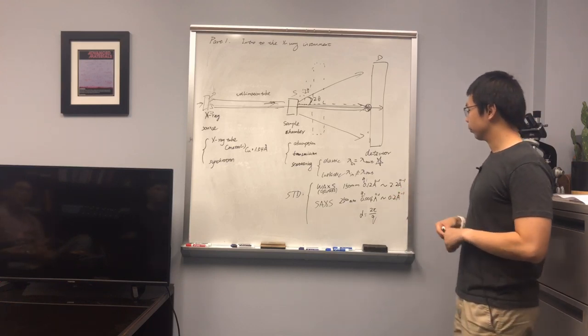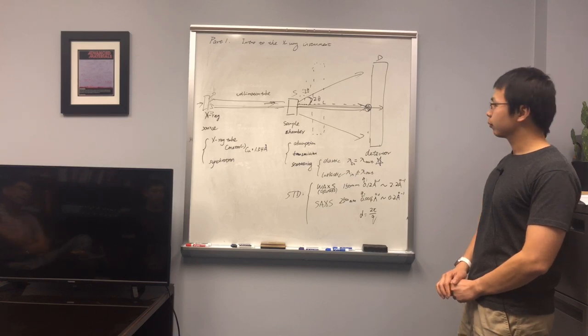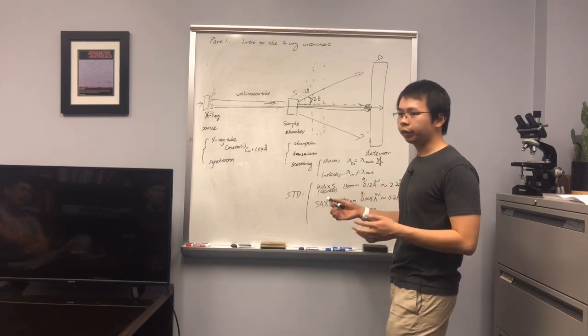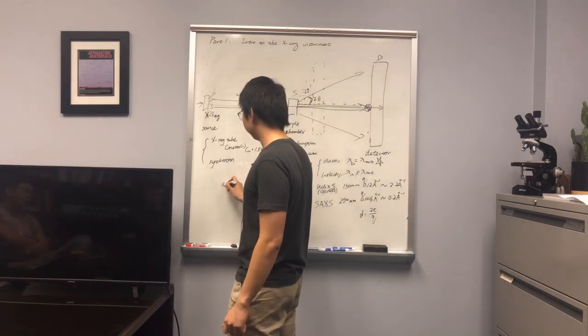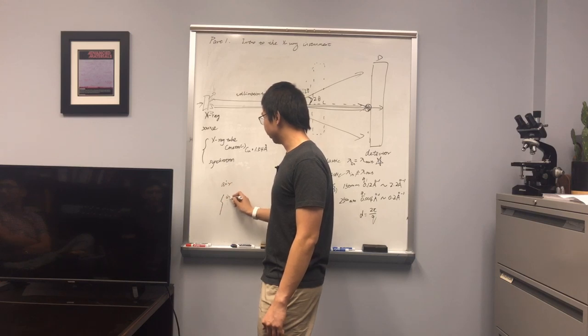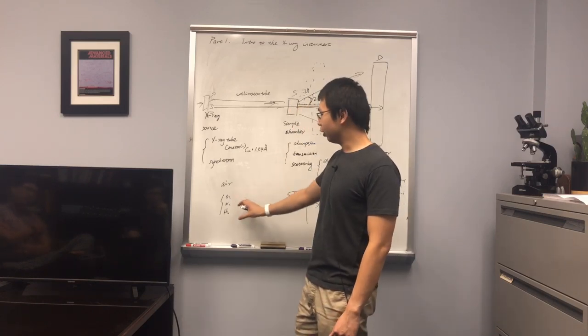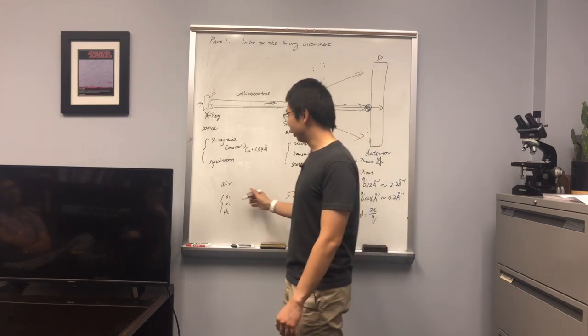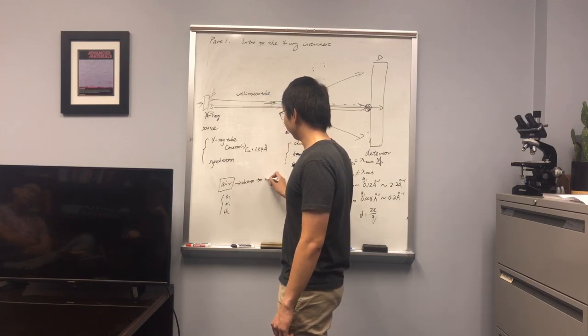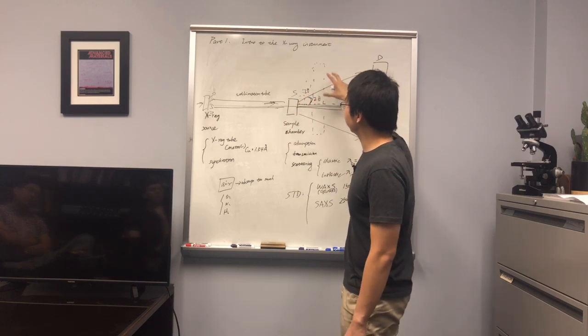Could you explain the importance of introducing a vacuum to the sample chamber? The difference between vacuum and ambient is simply air. Air contains oxygen, nitrogen, hydrogen, and other elements—each with electrons—so air causes absorption and scattering. What air does is absorb too much x-ray so there isn't enough reaching the sample, and even the scattered x-rays can be absorbed by air. Additionally, air creates a background scattering signal on the detector.